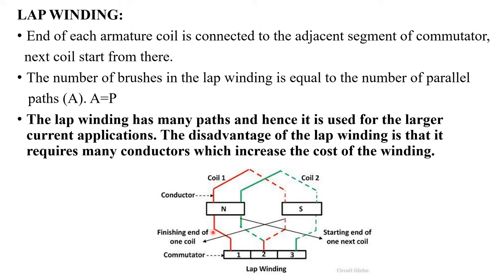This will be the starting end of coil 1, and this portion will be the finishing end of the first coil. This region will be the starting end of the next second coil, and this will be the finishing end of the second coil. In lap windings, the number of parallel paths will be equal to the number of poles. Due to the presence of more parallel paths, lap windings are normally used for high current, low voltage applications.